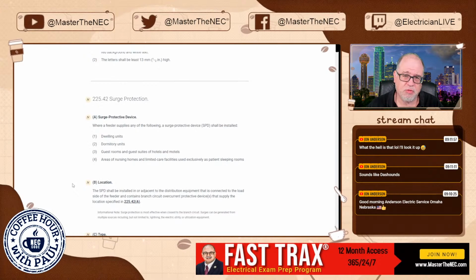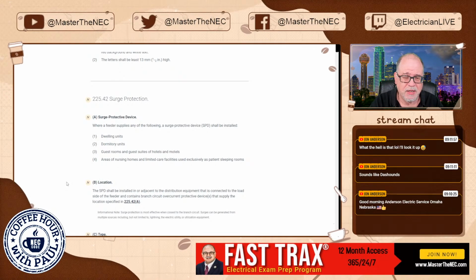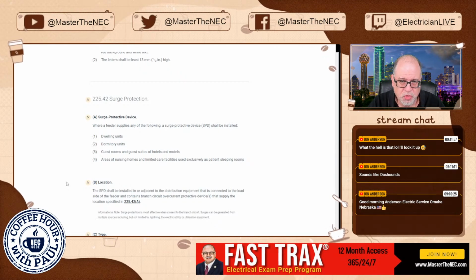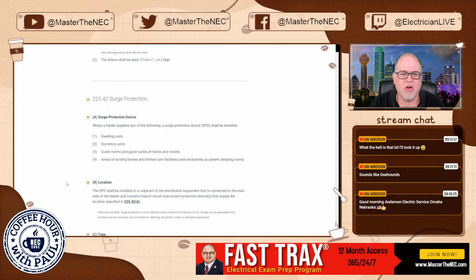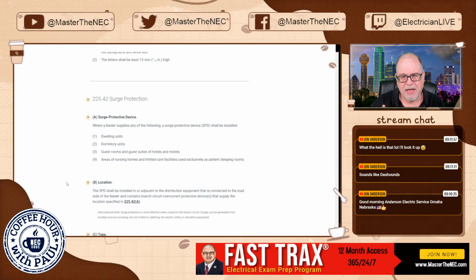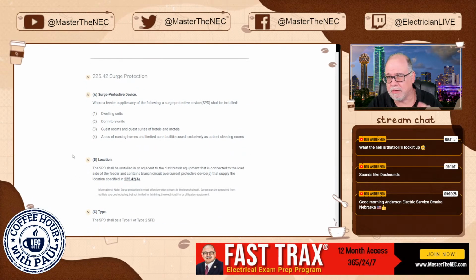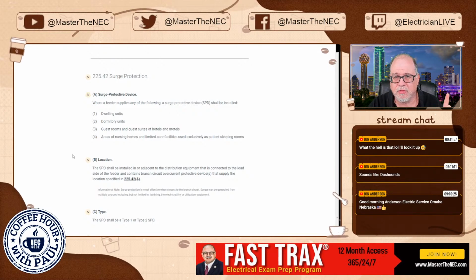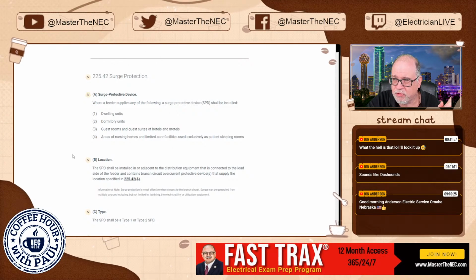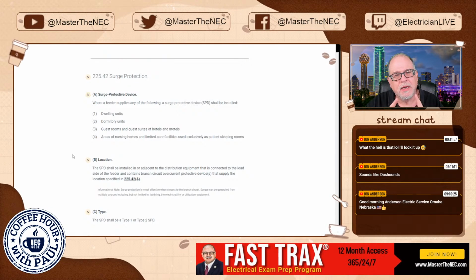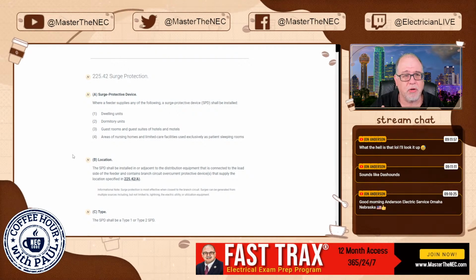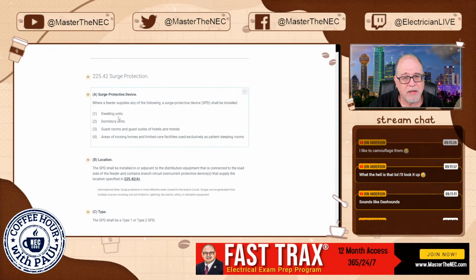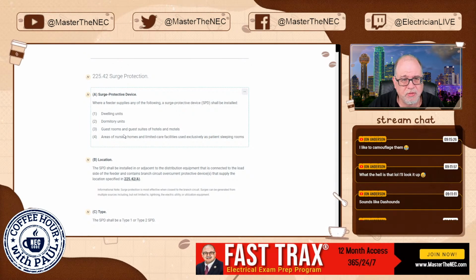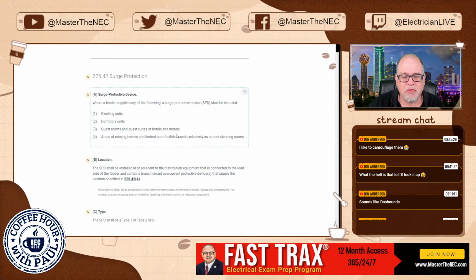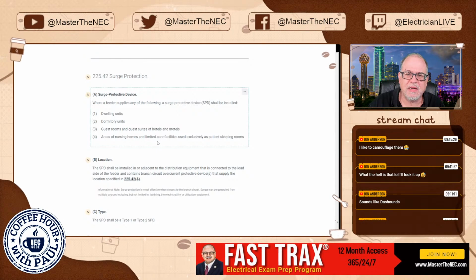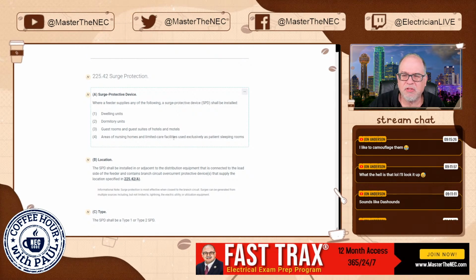The next significant change we have for feeder applications is, you guessed it, surge protection. So 225.42 is now going to require surge protection on specific applications. Now, here's where it's going to be required. Y'all know that it's already required for single-family dwellings and two-family dwellings, right? Already required, I believe, in 230.67. Well, now surge protection is required for the feeders that supply the following: dwelling units, dormitory units, guest rooms and guest suites of hotels and motels, and areas of nursing homes and limited care facilities used exclusively for patient sleeping rooms.